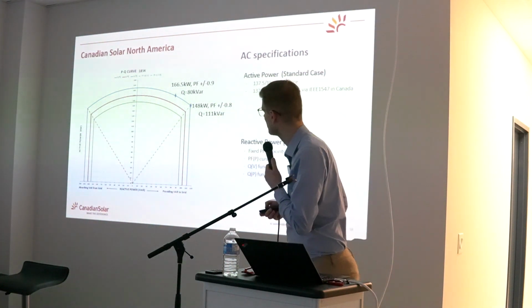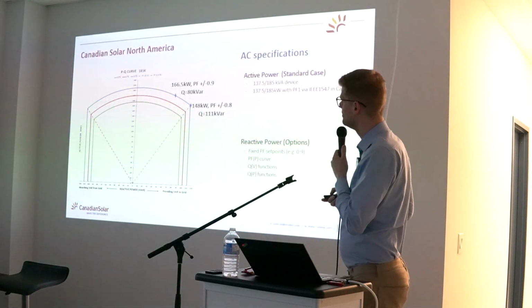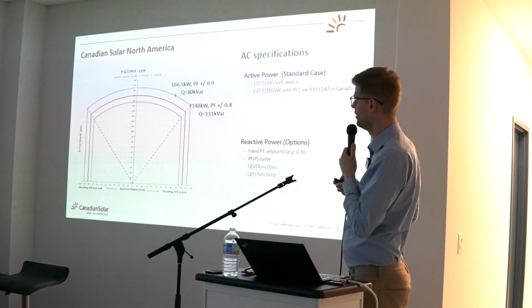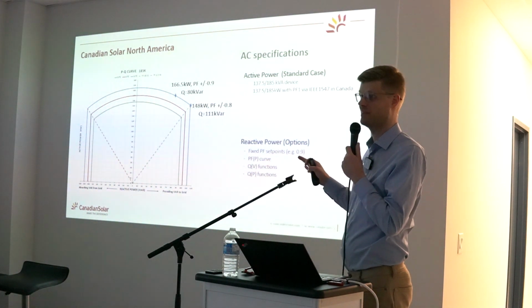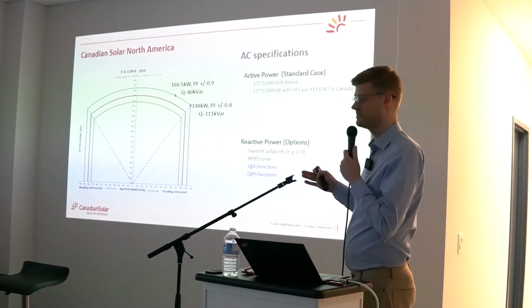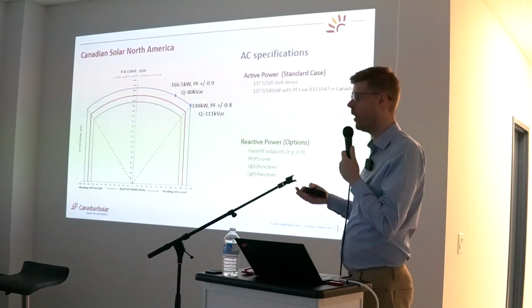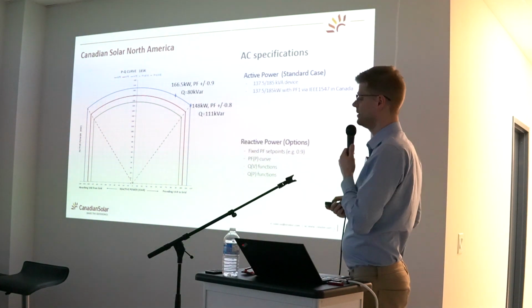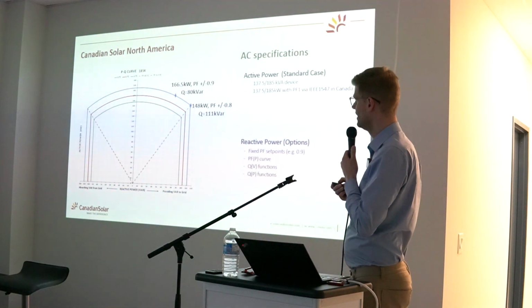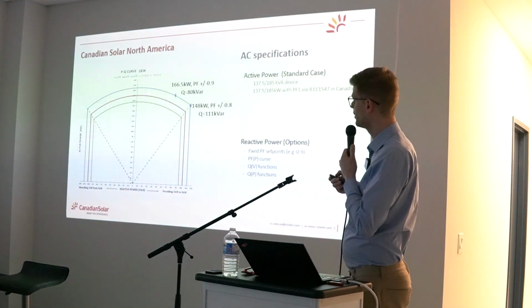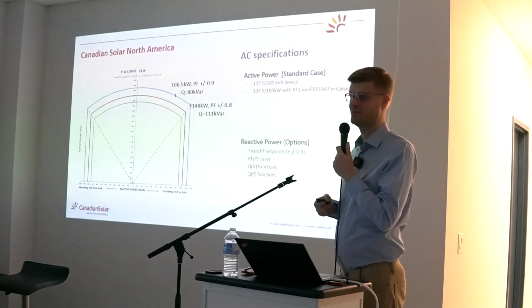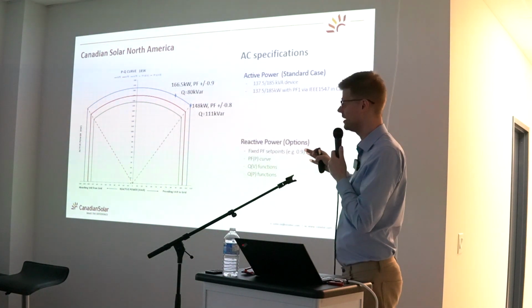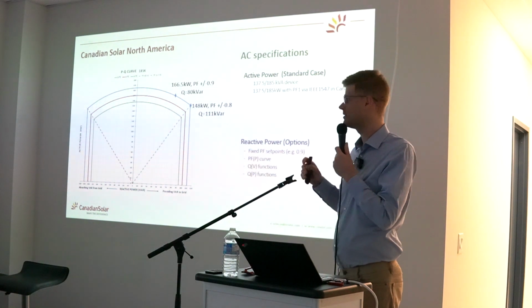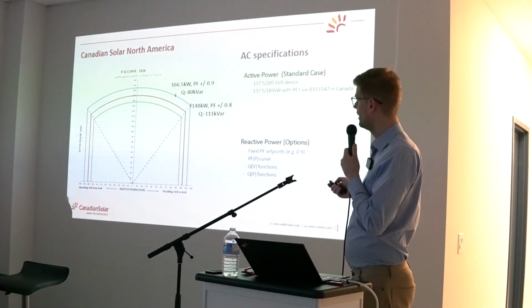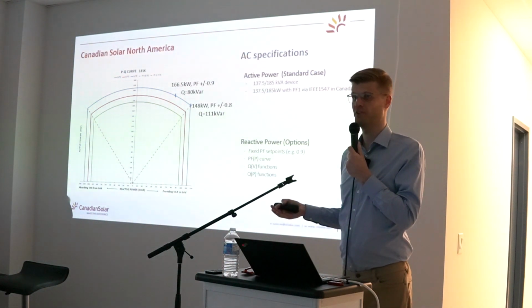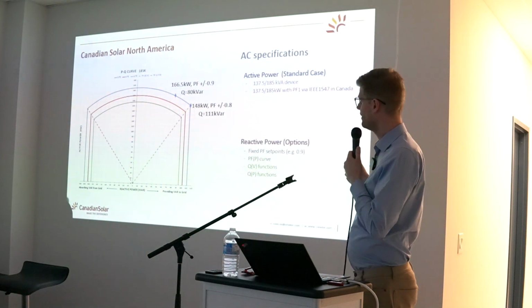And am I correct? Yes. And you will see you have the 185 kilowatts available if you are providing 0 reactive power. Perfect. However, Canadian code is developing, and we see more and more utility companies require a power factor that is not unity. So now they tell you, please use 0.9. And all of a sudden, at 0.9, you're somewhere here, and your power goes down to, whatever that is here, 166 kilowatts. So you buy 185 kilowatts, but with the requirement of the utility company, you can only actively use 166, because the remainder in that equation gives you the 80 kVAR reactive power that the utility company is requiring you to have. And for the 185, you have that reduction.